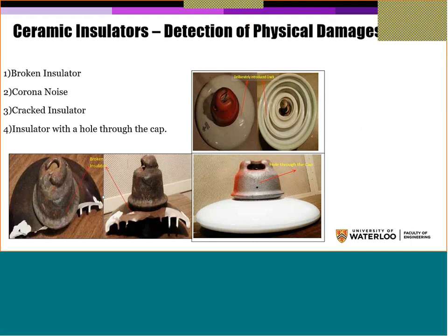So here we have these insulators with some of the problems. As I said, there is a surface crack here. We made that crack deliberately because we wanted to see it, and we also made a void. There is an internal void here. So we have a broken insulator as well. Here, this is a damaged, broken insulator.